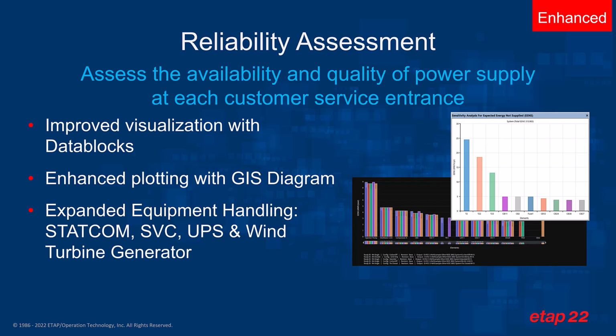Reliability assessment allows you to assess the availability and the quality of power supply at each customer service entrance using single or double contingency methods. Reliability assessment in ETAP 22 has been enhanced with improved visualization through data blocks. We've also improved the plotting through the GIS diagram and expanded the equipment handling to include STATCOM, static var compensator, UPS, and of course wind turbine generators as part of your reliability assessment in the electrical system network.